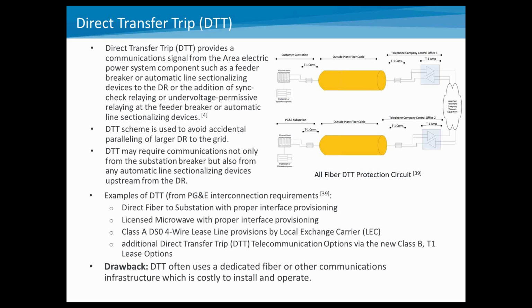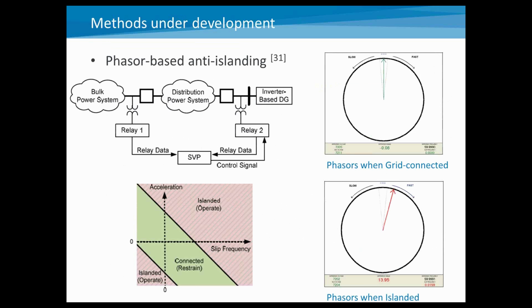So I'm sure we'll talk about this a little later on in the questions. An additional method that's under development looks at the phasor measurements both at the distributed generation and at the bulk power grid, and basically uses phasors to understand if the islanded condition occurs. So if they are interconnected, you'll have no phasor difference between the voltages on the system. As soon as you have an island, you'll probably have some drift there because of different load and DG requirements, and you'll start to see some kind of voltage differential, and that would allow you to detect this. Again, for this type of system, you will need some type of communication in addition to the phasor measurements.